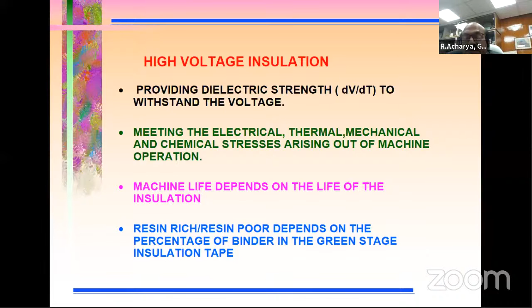This insulation system, whatever I mentioned a few slides before, that paper or mica or this and that, in fact, if you just look at the insulation of a large capacity high voltage stator winding, they are composite insulation. Mostly they're all mica based insulations: mica, glass, and the resin. Even though each and every material here has a dielectric property, they have a predominant share in the overall perspective of the insulation.